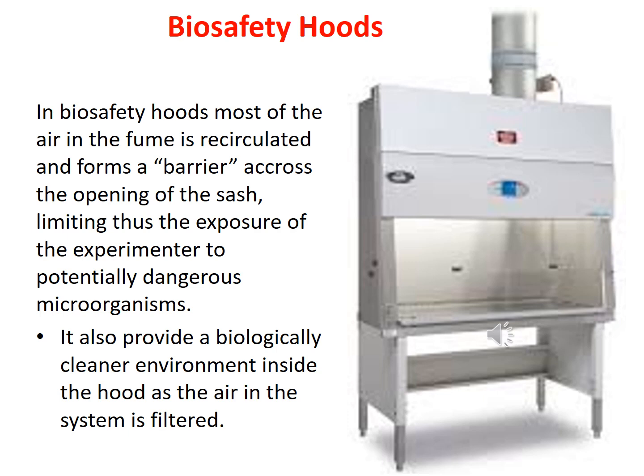In biosafety hoods, most of the air is recirculated and forms a barrier across the opening of the sash. So there are different sash openings here, and in this way it potentially provides microorganism protection to the worker. Also, since they contain very specialized filters inside these biosafety hoods, they provide a clean environment, because the air is filtered inside these hoods. I think I will show you a couple more examples of these filters in coming slides.